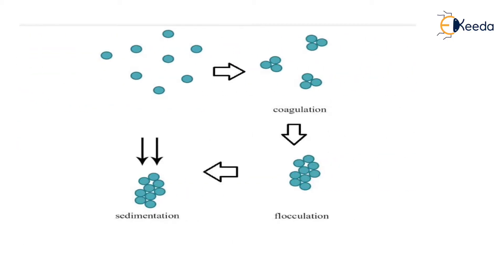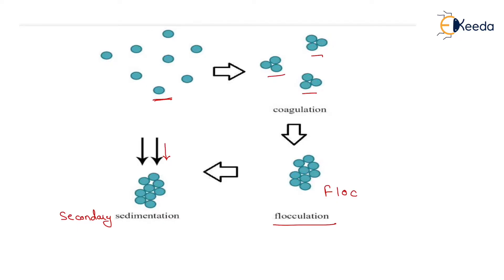Suspended impurities will be there; when we add a chemical, charge neutralization will occur. When charge neutralization happens, in the flocculation step all the particles will come in contact with each other and floc formation will take place. When we send it to the secondary sedimentation process, the flocs will settle down due to their self weight at the bottom of the tank, and water will be free from that type of impurity. That is the whole procedure of sedimentation aided with coagulation and flocculation.